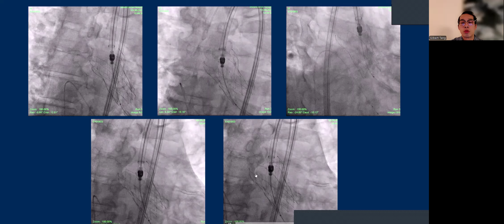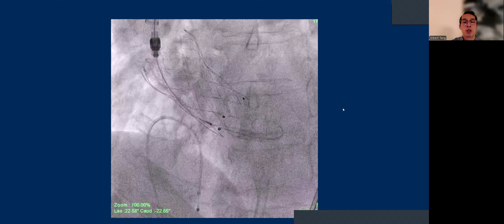And so here's how it looks. We go into more LAO view, and you can see it's separated. So do not pull before you can see that the delivery catheter and the spindle where the tab is actually released from the tab. And you can see that here the nose cone is also centered with the stiff wire. Pull back so you don't end up with the nose cone on release dragging the valve out, because it interacts with the inflow of the frame causing the pop out. So this is very important.